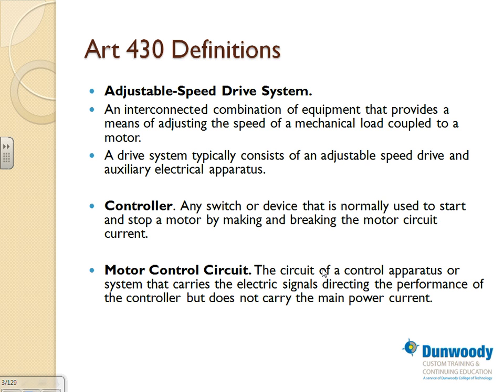I call them the poor man's way and the rich man or woman way. The poor man's way is you throw all your disconnects, magnetic starters or VFDs on the wall, with a gutter at the top, and you tap from a feeder, right? You bring a feeder and tap from that feeder, and feed multiple VFDs or multiple magnetic starters with their own disconnect, an overcurrent protection device, and overload, and you feed multiple motors or machines. That's the poor man's job. Cheap, easy, you throw them on the wall, they're contained separately on the wall.